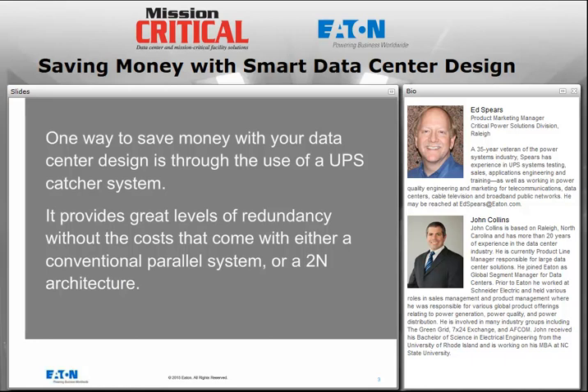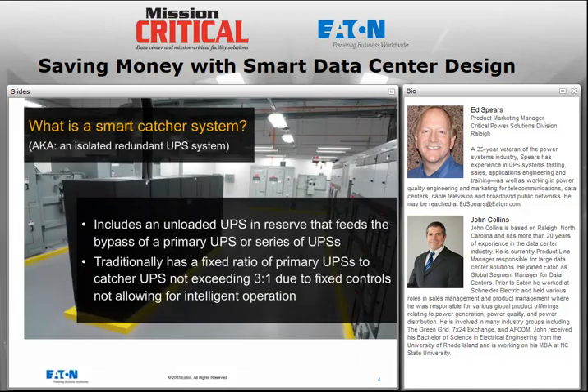We find, as our competitors do, that oftentimes the problem that may exist in a particular installation is often due to confusion on the part of the operator when they take an action where they're not sure what that action is going to do. So if the entire system and power flow can be simplified in such a way while still providing great redundancy, then that's a very good thing to be able to do.